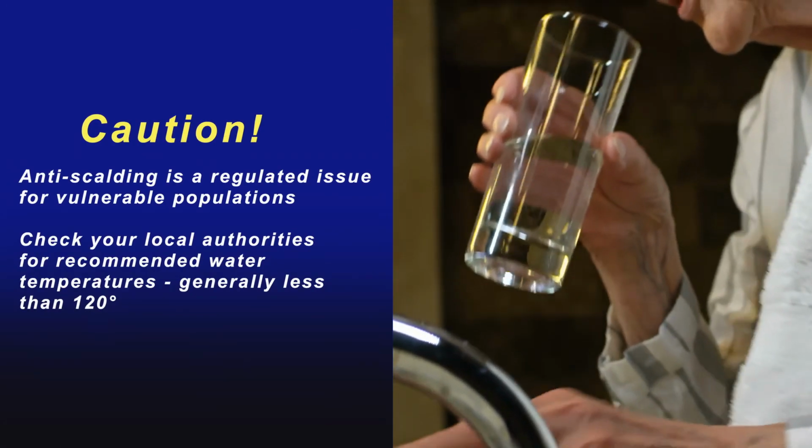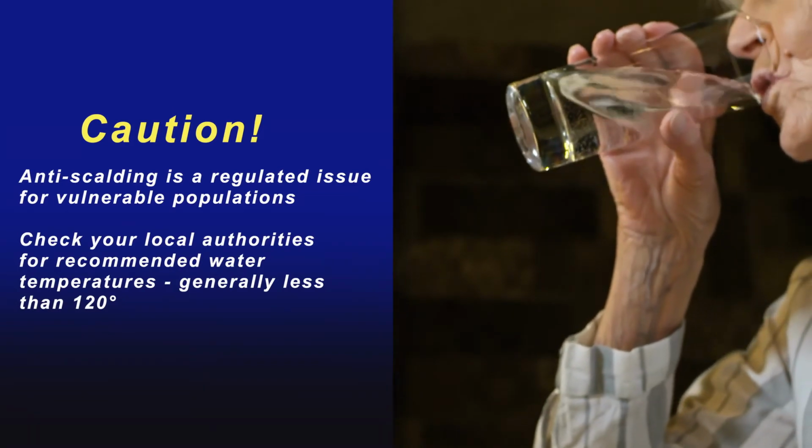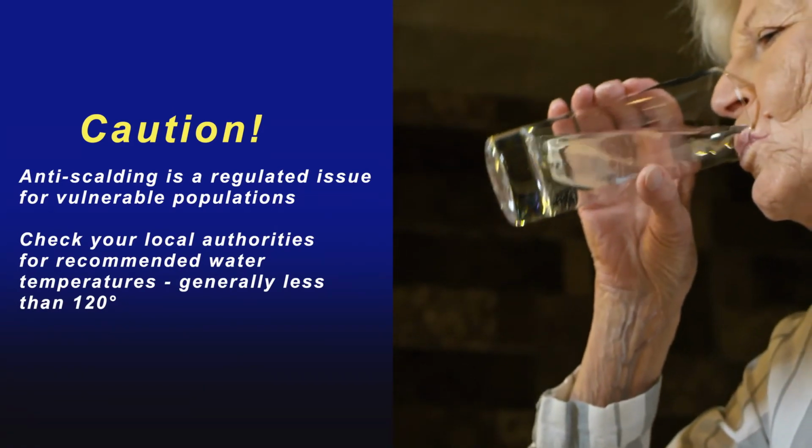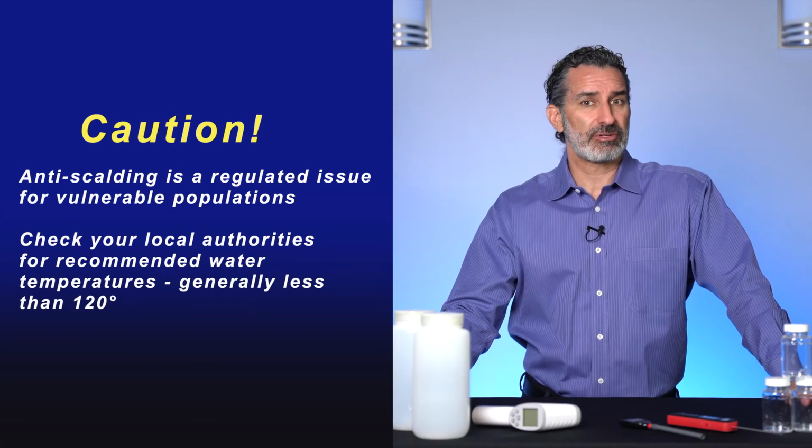For vulnerable populations, anti-scalding is a regulated issue, and you don't want to expose residents, such as skilled nursing facilities, to temperatures above 120 degrees, depending upon your jurisdiction.